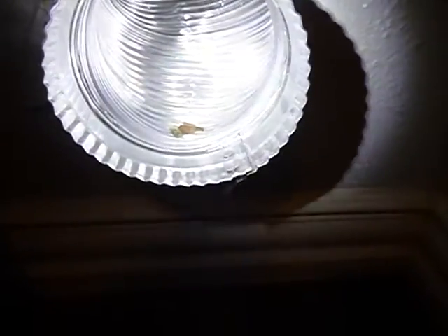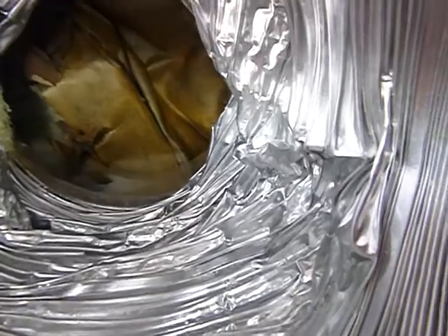Since we are in the laundry, there should be a label indicating how far this clothes dryer vent goes. You're not supposed to have corrugated material inside the wall. I've got a still image of this — I'm going to put some light in here and see. I can't even tell where it goes.